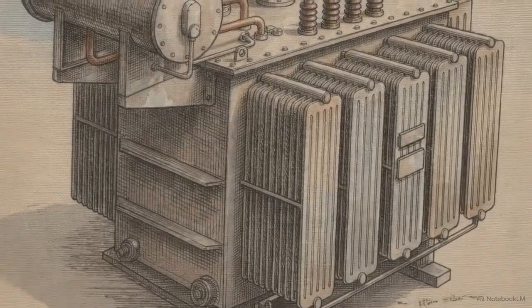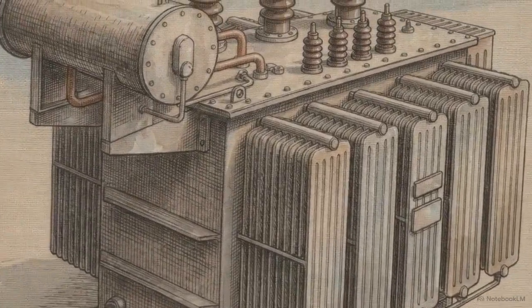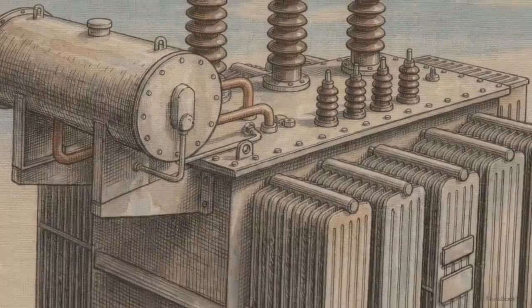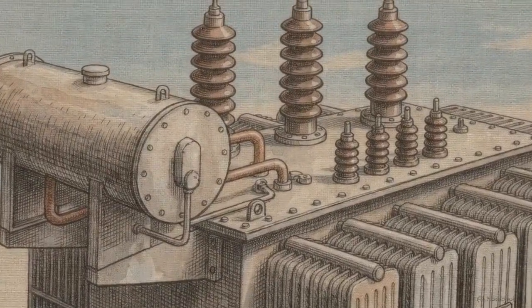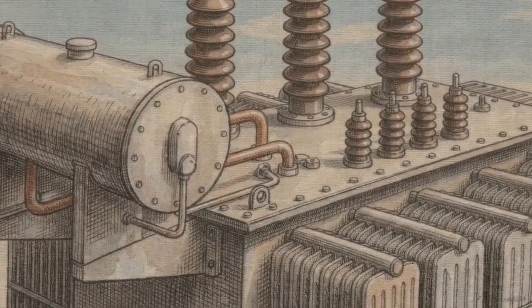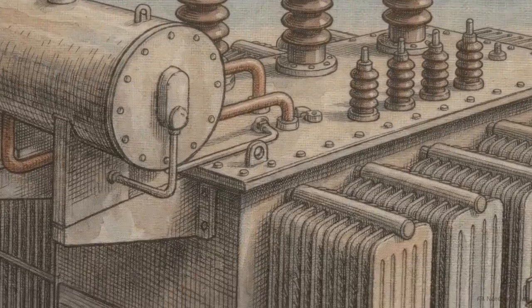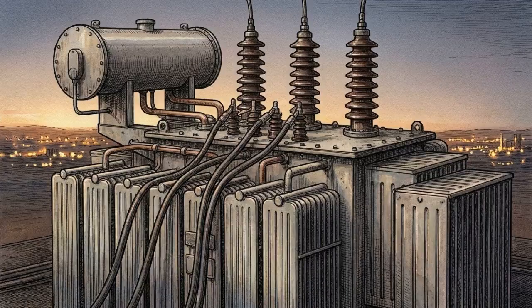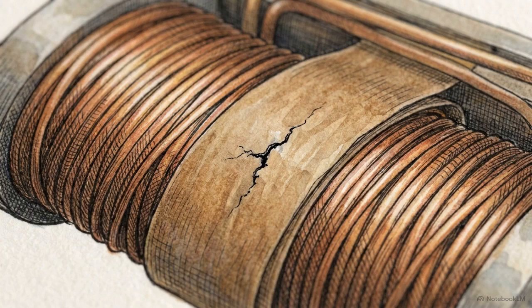Inside a modern substation, a 10 megavolt ampere 33 kilovolt to 3.3 kilovolt delta-Y transformer operates in a state of continuous thermal and electrical equilibrium. It routes enough power to supply a small city, flawlessly stepping down grid voltage 24 hours a day. But an internal insulation breakdown, even a microscopic phase-to-phase short, shatters that equilibrium.